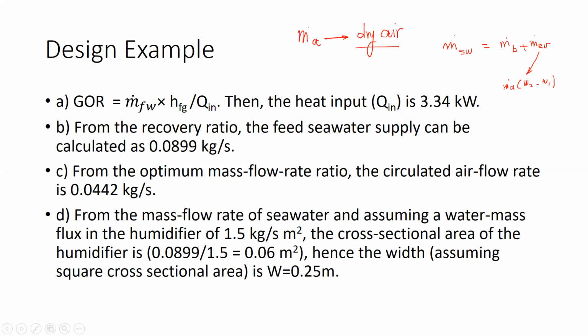Now we are going to make use of this information for sizing the unit. The humidifier is assumed to be either a cylindrical compartment — we used to do that previously, like get an 8-inch pipe and cover it from the top and bottom, then put a tube in, and a shower head so that it sprays the water — or it can be a unit of square or rectangular cross section.